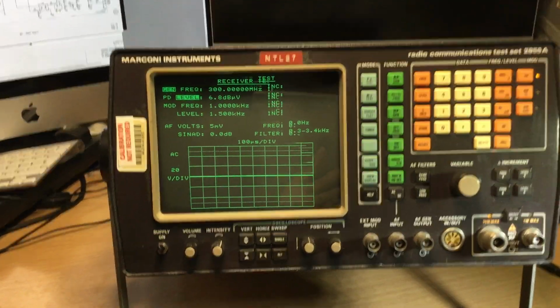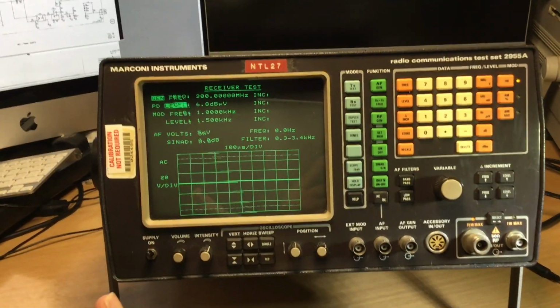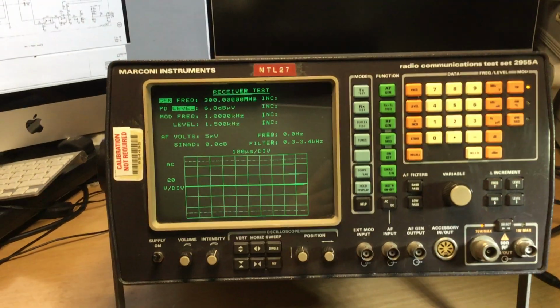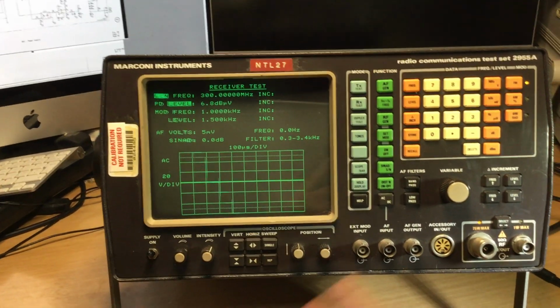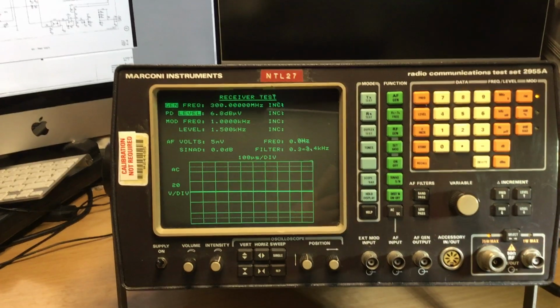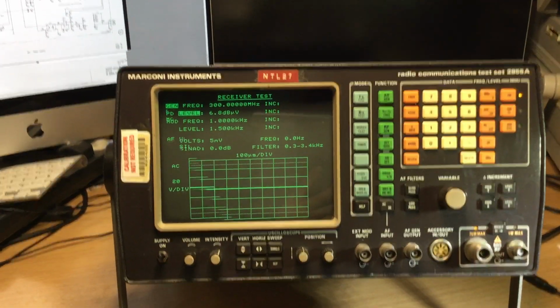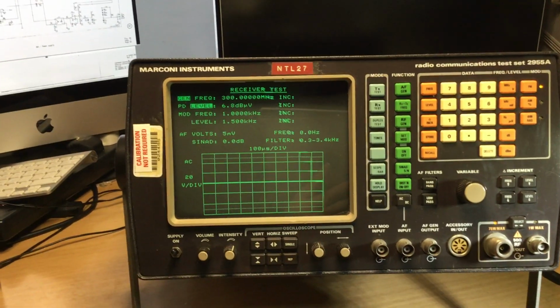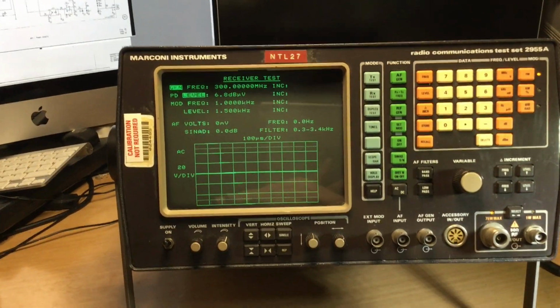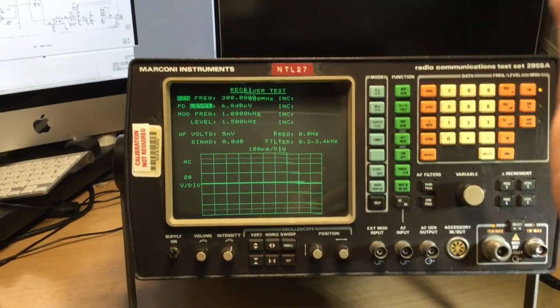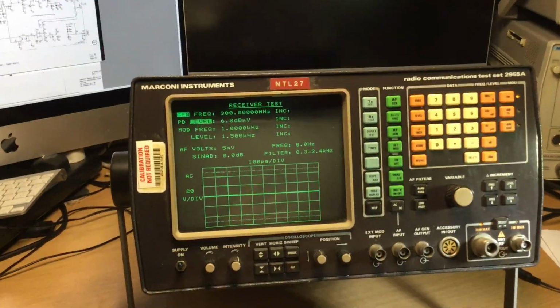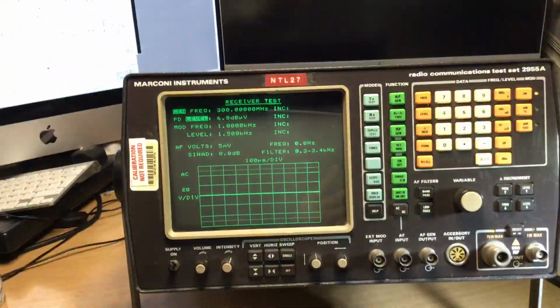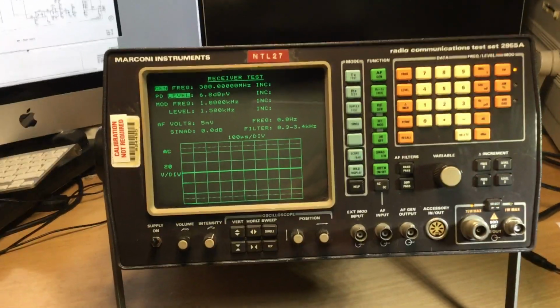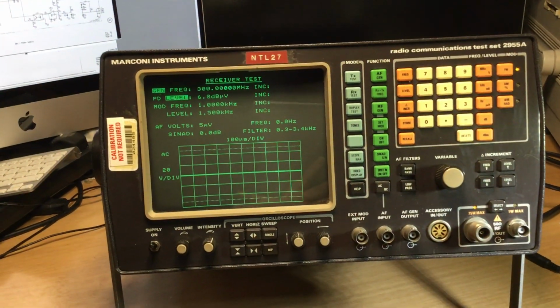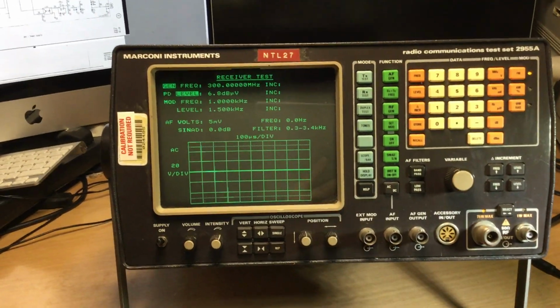That's a bit of a nightmare to calibrate on these, because we have to do not only the entire frequency range of the instrument, from basically 400 kHz to 1 GHz in multiple steps all the way across that frequency range, or the dynamic range of the test set, but we also have to do the levels going from basically 0, -120, -130, whatever dBm it goes down to, right the way up to the maximum RF level in 1 dB steps or whatever. So we have to adjust that in the software, and it's a very laborious, long drawn out process, and it takes lots of time to do that.